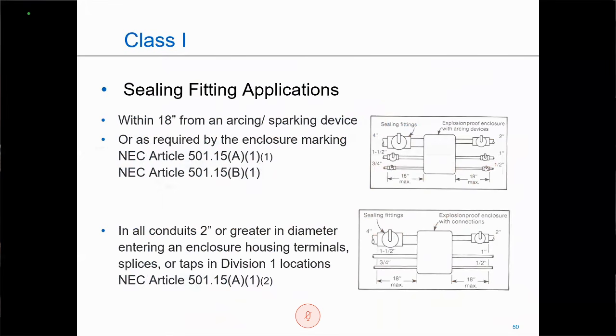So when I have an arcing source, we're referring to the top pictorial here, an arcing source such as a motor starter, that when it's installed in a Class 1 Division 1 or a Class 1 Division 2 area, each individual conduit entering and exiting is required to be sealed within 18 inches of that unit. And then in 2017, the National Electrical Code added a new statement, "or as required by the enclosure marking." And that is because there are times that some manufacturers will have sealing fitting requirements that are more strict than the National Electrical Code's 18-inch rule.